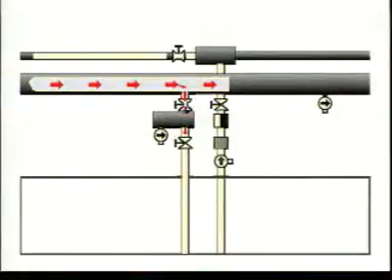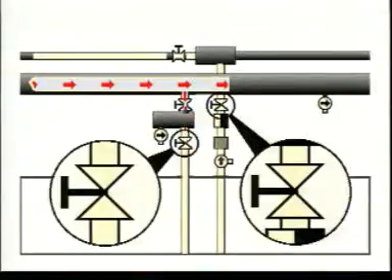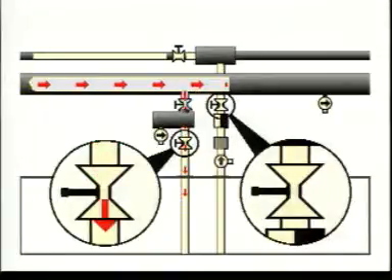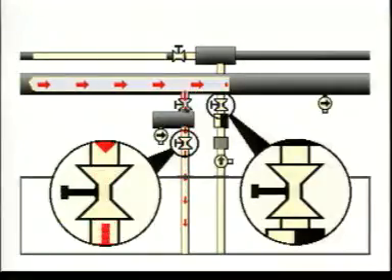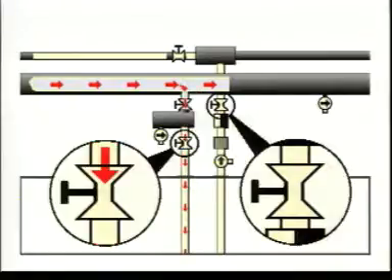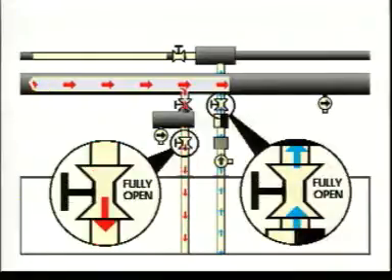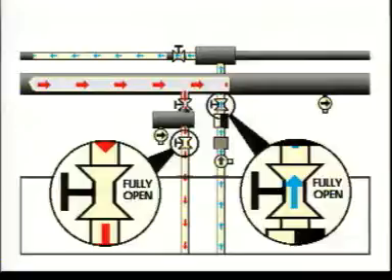Now the temperature is falling and it's time to activate the coils. The inlet valve is fully opened and the return valve is partly opened at first. After a while, when water is flowing through the return drain, the return valve is fully opened and the return drain is closed.